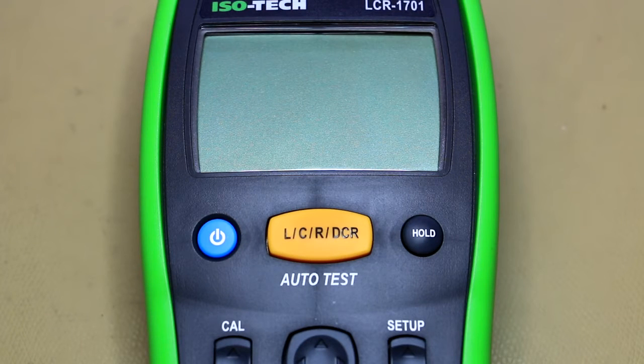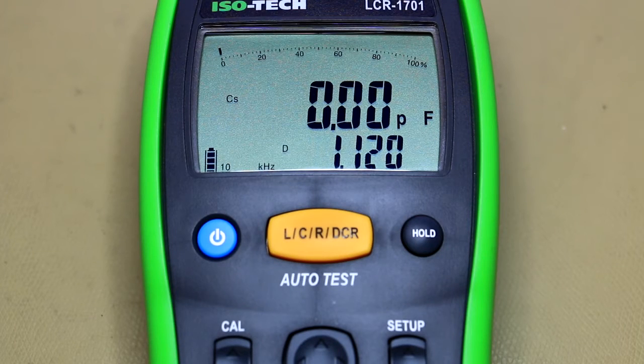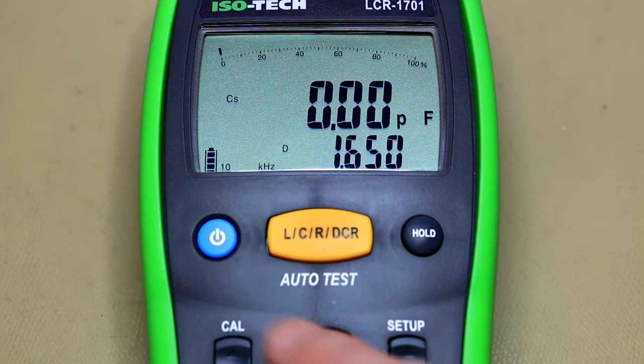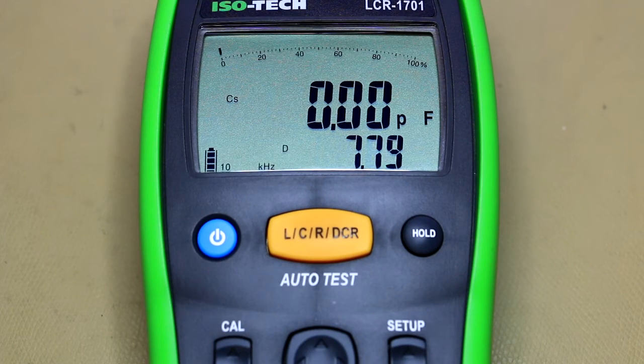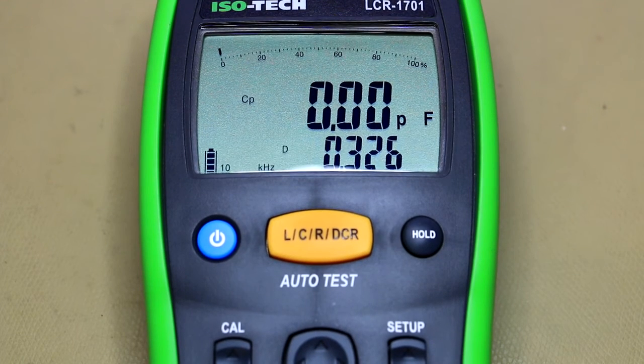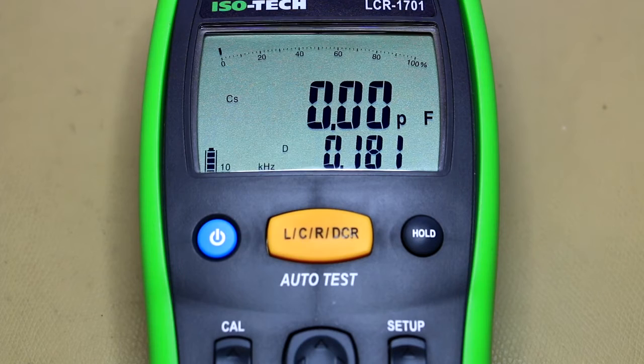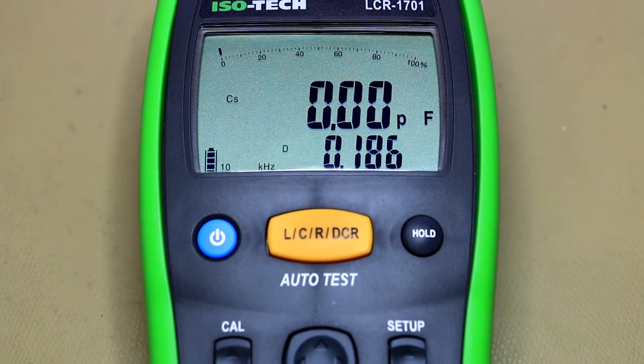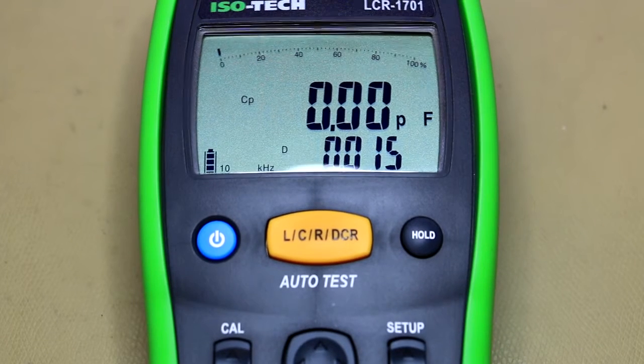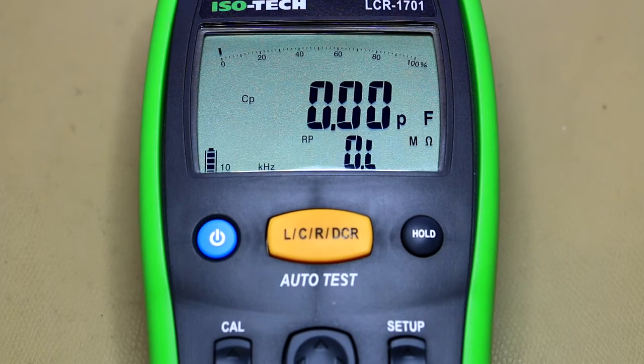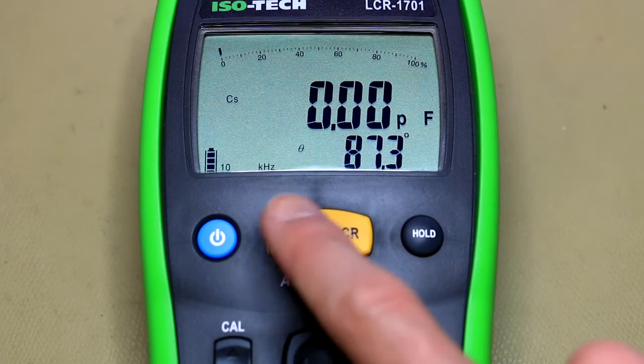So let's run through the most common modes of this meter. Turning it on, the 10K shows it's the 10 kilohertz version. Of course you also get the 100 kilohertz version. It starts up in the last setting that you used it in, which currently is the series capacitance mode. You can of course set it to parallel mode, back to series mode, and then also you can measure the D value, Q value, ESR, and the phase angle. And of course in parallel mode you get all those values, but you can also measure the parallel equivalent resistance.